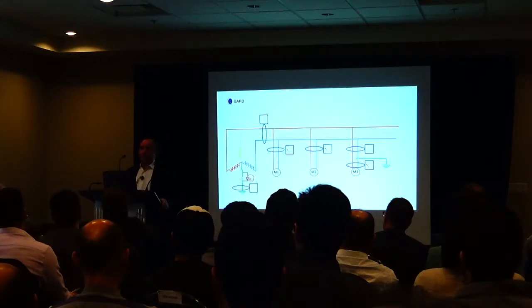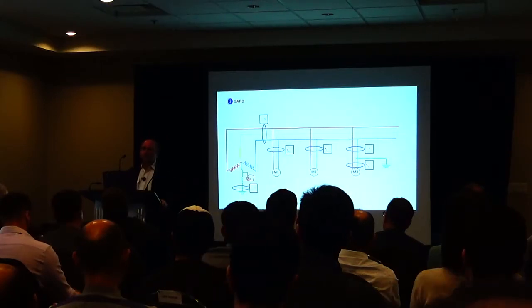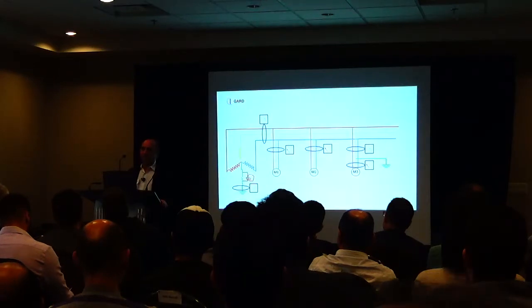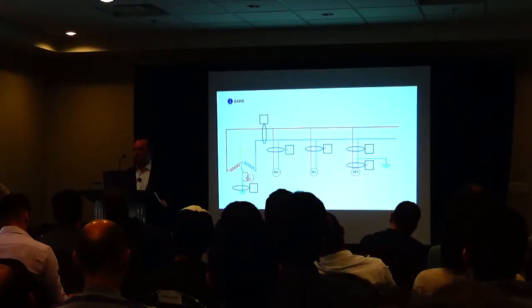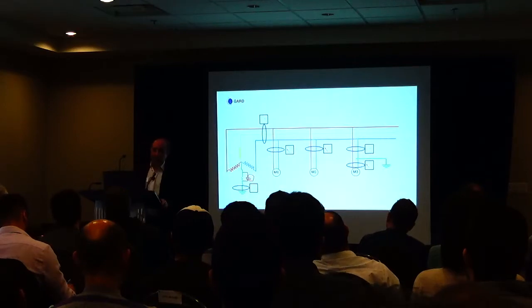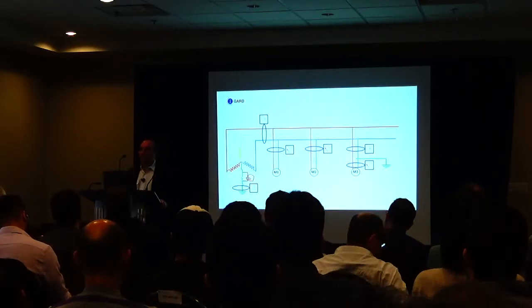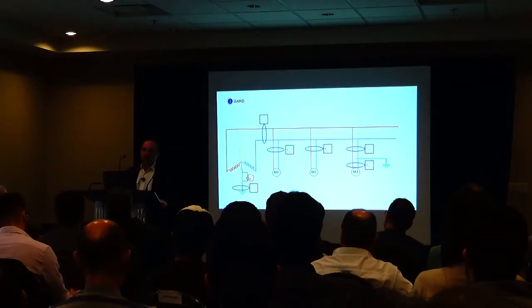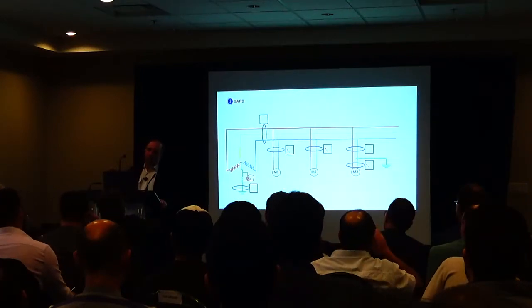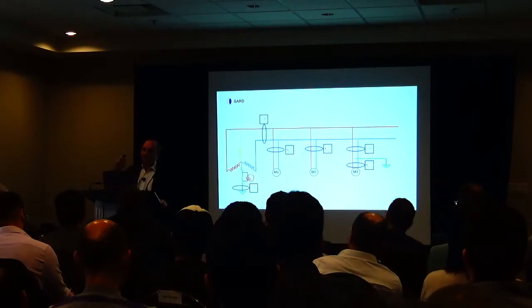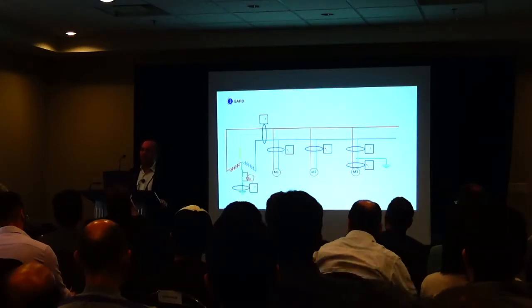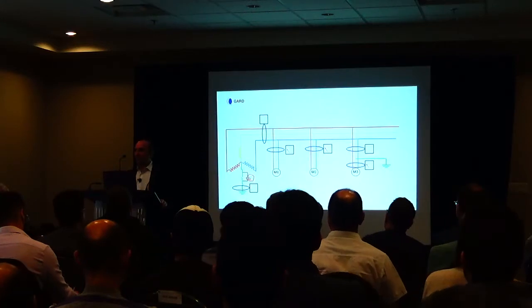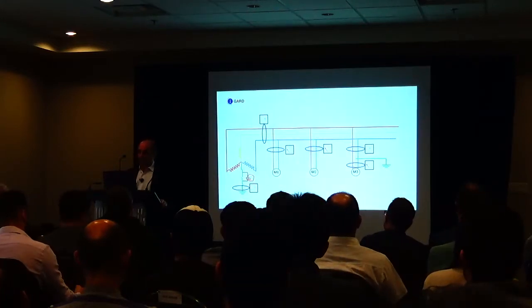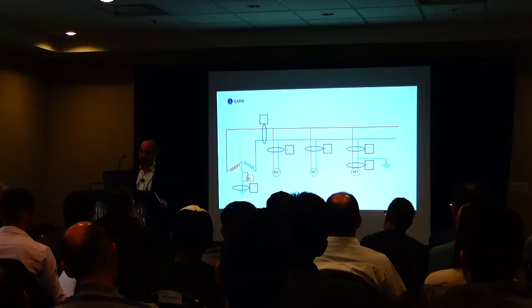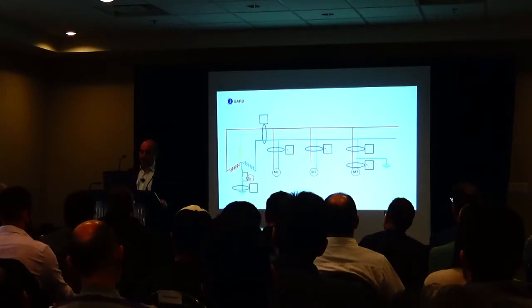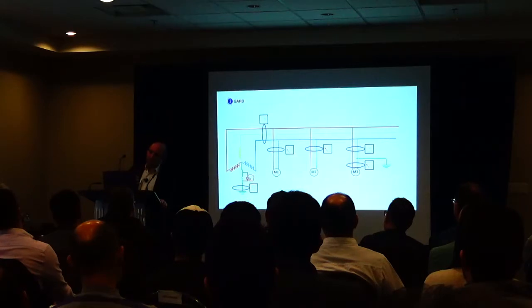Right. And we had one facility in the United States who converted over 100 substations from solidly grounded to resistance grounded solely as an arc flash mitigation technique. And what they found is they saved more money in 3 years on motor repair costs than more than paid for the capital investment of all those resistance grounded systems. So you have much less damage at the point of the fault. So it is worth it, but you have to look at your facility. Yeah.